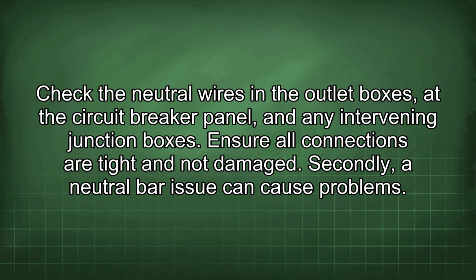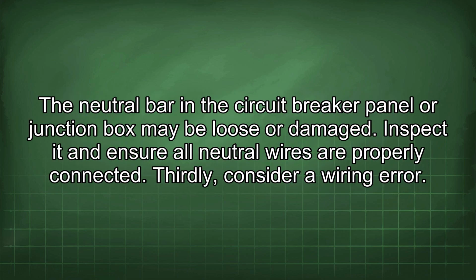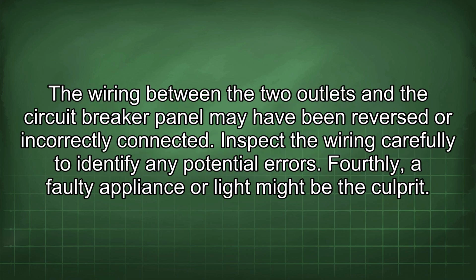Secondly, a neutral bar issue can cause problems. The neutral bar in the circuit breaker panel or junction box may be loose or damaged. Inspect it and ensure all neutral wires are properly connected. Thirdly, consider a wiring error. The wiring between the two outlets and the circuit breaker panel may have been reversed or incorrectly connected. Inspect the wiring carefully to identify any potential errors.